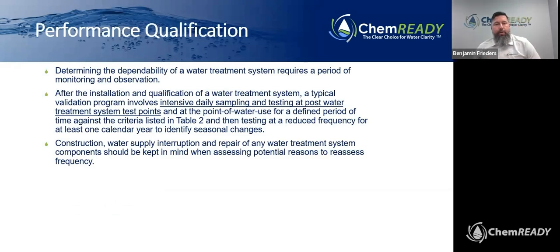So when it comes to the performance qualification, what this section in the standard means is, there needs to be monitoring in place to verify that your existing critical water system or the system that you just installed are going to meet the specs that you need to meet the standard. Okay. Part of some of the conversations that we've had with customers, their eyes get really big and they see the dollar signs this is going to take to implement.